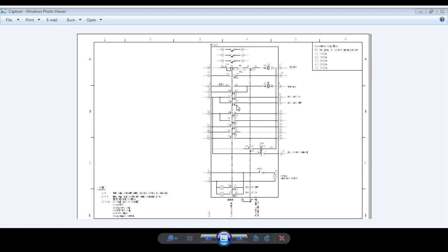Breaker ON/OFF indications are required in the panel. So on the control panel of the fixed part of the panel, there will be indications of breaker ON/OFF. That will be wired through these contacts. This is a normally open contact. When the breaker closes, the breaker main contact closes, this auxiliary contact will also be made and closed, and the breaker ON indication will appear in the panel.